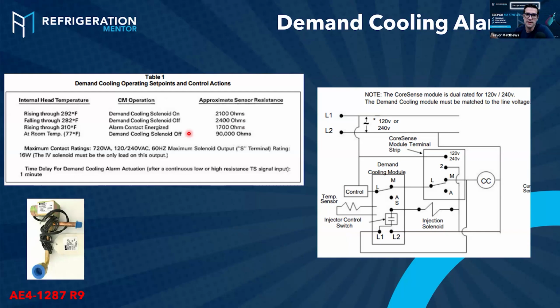And then you got to test this stuff. This is no different than any temperature sensor out there. You got to test it. This one here, you use resistance. There's some that you use voltage. It all depends on the type of, that's a pressure transducer. I was thinking of something else. But use your ohm meter at room temperature, 77 Fahrenheit, 25 Celsius, should be about 90,000 ohms. Super important to look in these manuals.